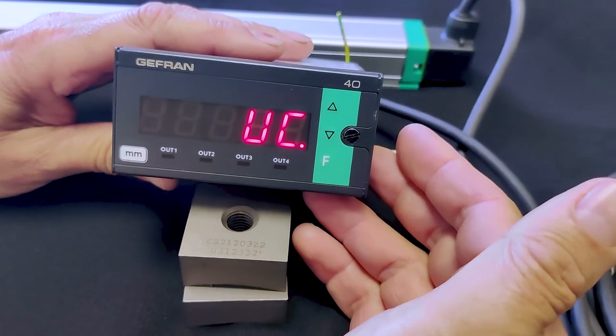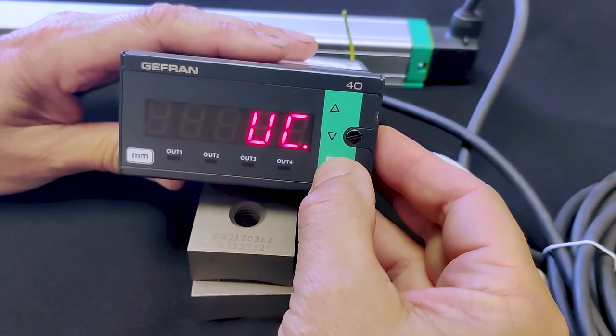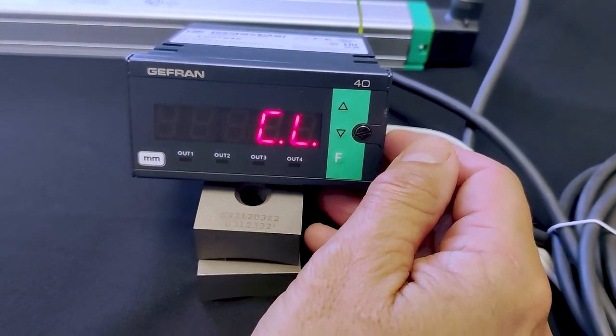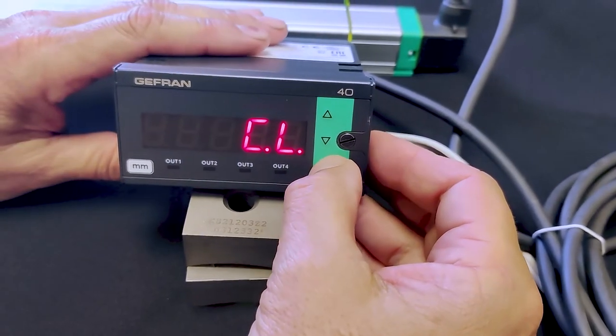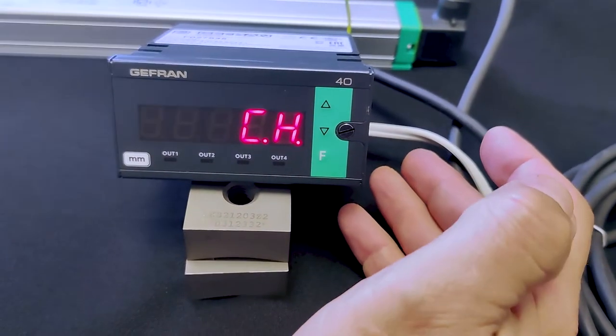Press and hold on the F key until you get to UC. For a potentiometer you put in number 2. CL is the low limit calibration. So we're fully inserted. Let's press and release F.